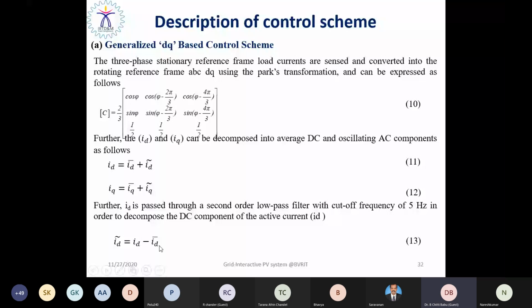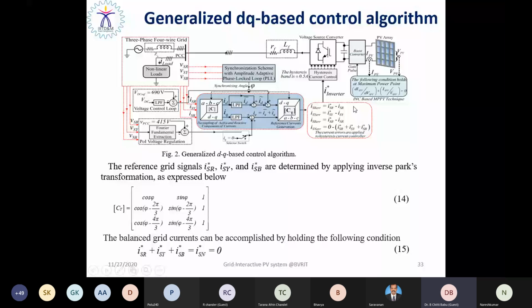And this is the control strategy, with the output given to the boost converter, and the boost converter output is available in the DC link capacitor. Then the DC power will be inverted into AC with the help of the voltage source converter through the interfacing inductor. Then the active power or controllable power is injected into the utility grid. So at the point of common coupling, PCC, right, when a non-linear load is connected, the current is distorted. So we propose a control algorithm.